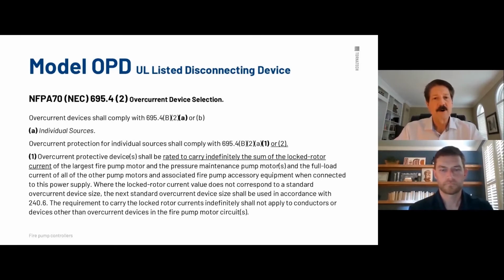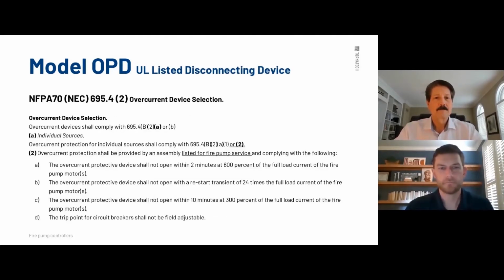Again, we can reference all these. I'm not here to bore you, but it's repetitive, rated to carry indefinitely the sum of the lock rotor current, 6 times full load amperage. This device being OPD, the circuit breaker design, is 120 seconds. And this just reiterates what I just mentioned. 2 minutes at 600%, restart 24 times, 10 minutes at 300, and cannot be field adjustable.